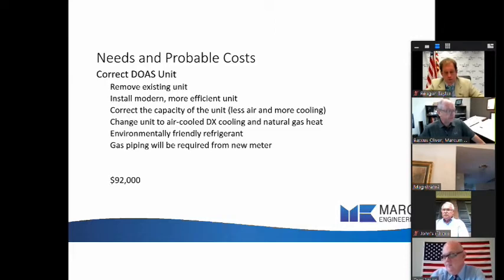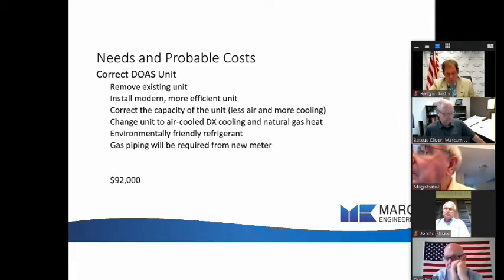Third, I would correct the DOAS unit on the roof. I would remove the existing unit. I would install a more modern, more efficient, and a right-sized unit. I would correct the capacity of the unit, moving less air and providing more cooling. I would change the unit to not be on the water system anymore, but make it an air-cooled machine using the natural gas that's on the building. So I'd be running a gas line up to the roof to allow it to have the heat ability. We would then have an environmentally friendly refrigerant that's cheaper to recharge. I've already talked about the gas pipe. So the earmark for this would be $92,000 for correcting DOAS. Remember, this is the unit that I believe is causing the biggest problems to comfort.